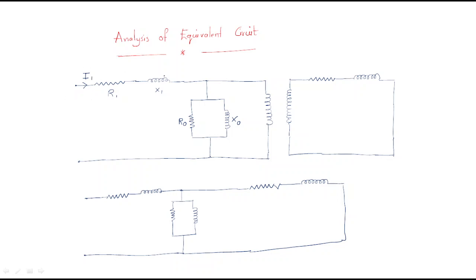The generated EMF in the primary winding is E1, and the current entering into E1 is I2-dash. The current entering into the no-load branch — before the no-load branch — the current entering into the core loss component is Ic, and the current entering into the no-load reactance is I-mu, the magnetizing current. The combination of both the core loss component Ic and the magnetizing component I-mu gives us I-naught.